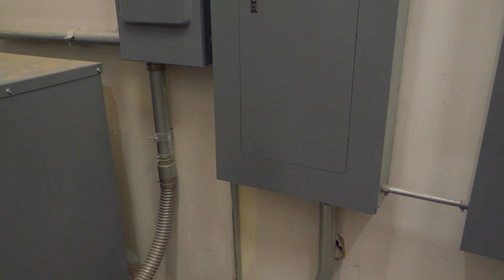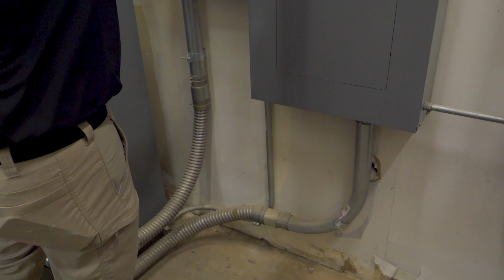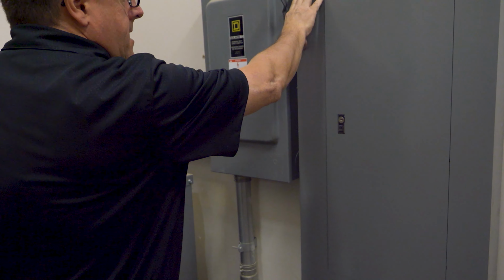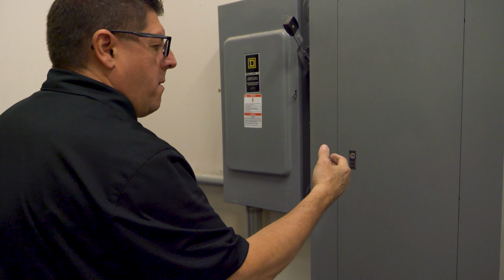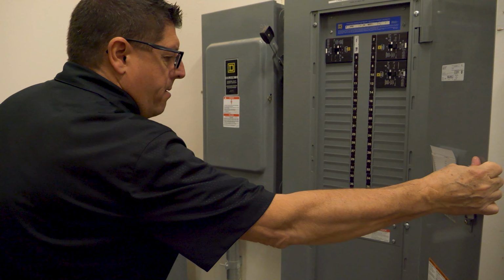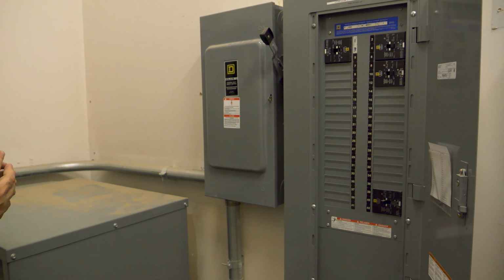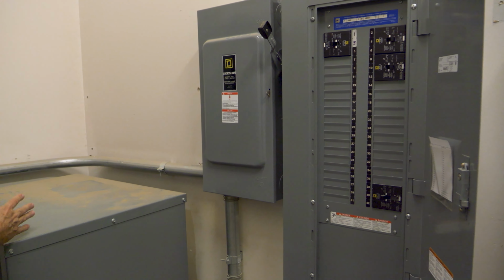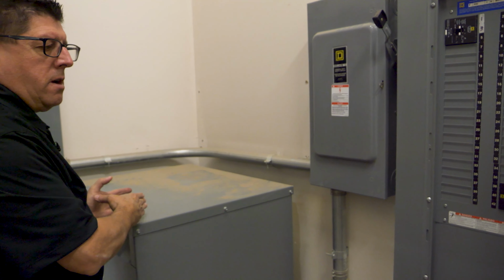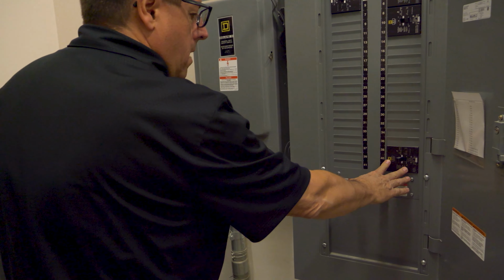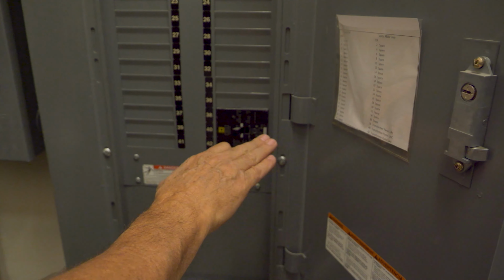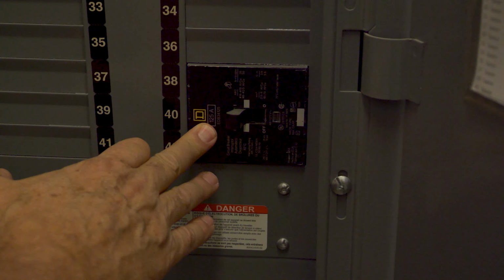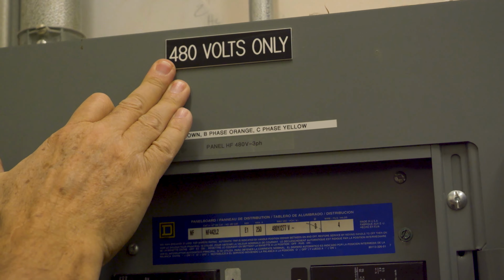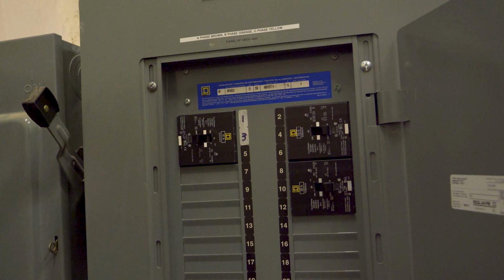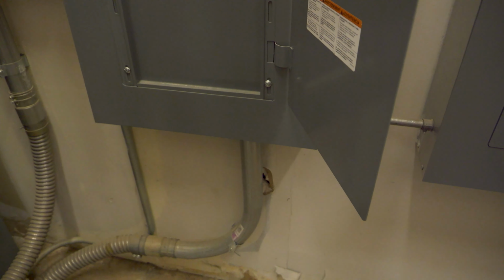So identifying the incoming current, I need to inspect this panel. Verify that it does not have any stray current by using my right hand, opening it up, and identify the breaker that is servicing this transformer. This breaker is here. It is a three-phase, 125 amp, 480 volt breaker. The conductors follow through this conduit into the transformer.